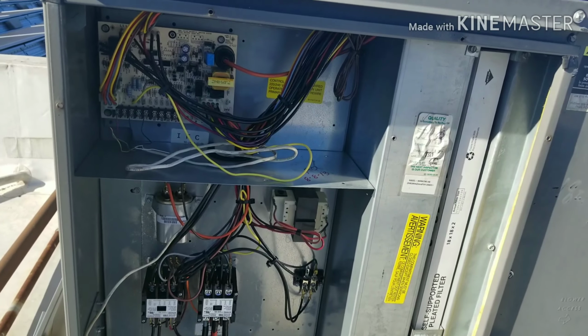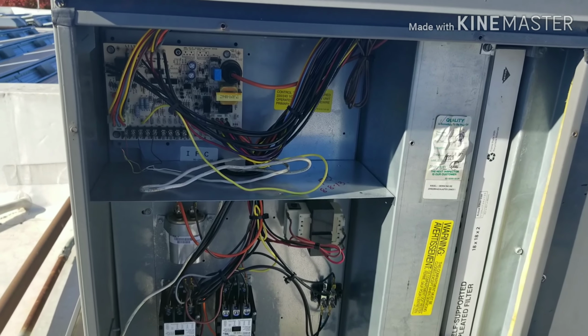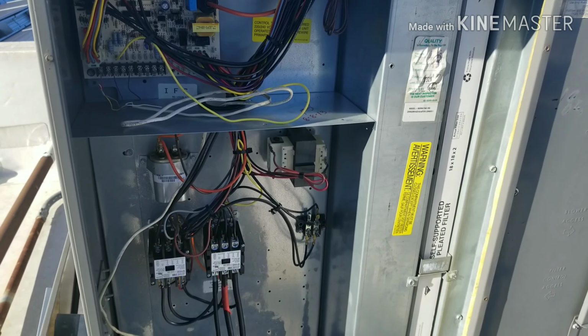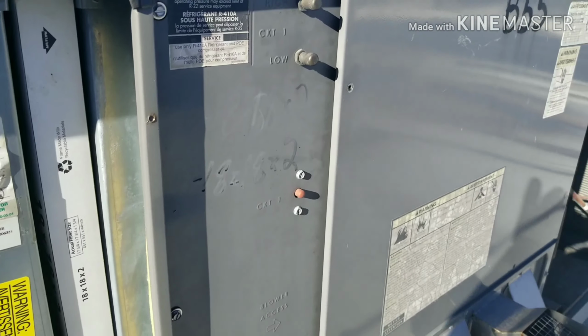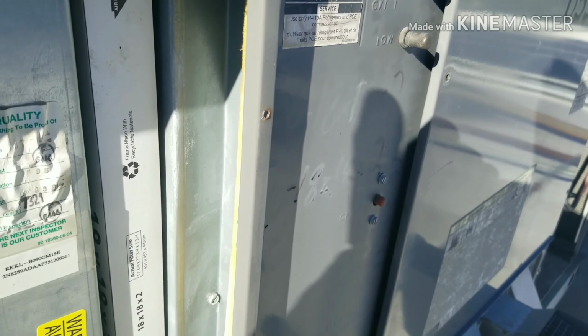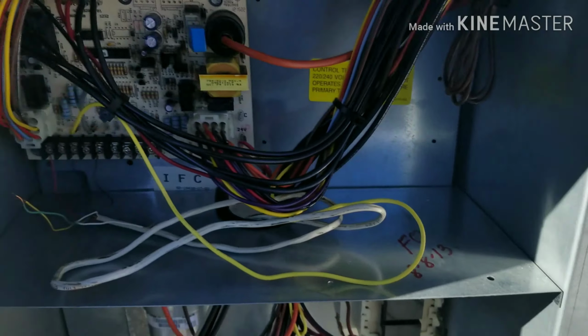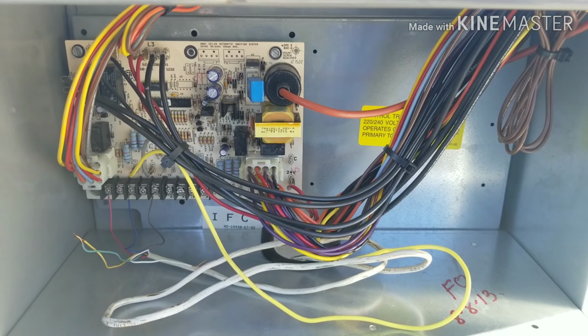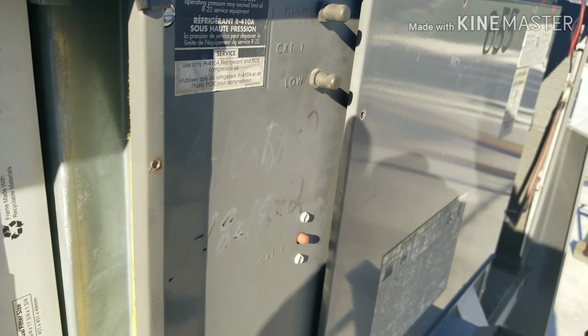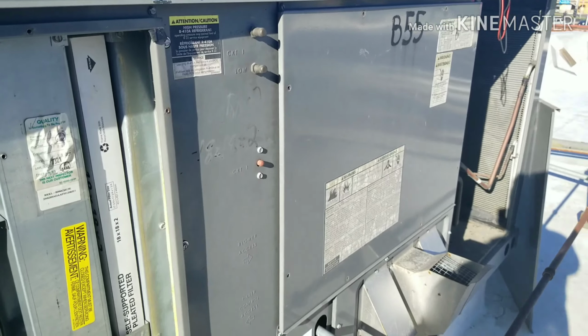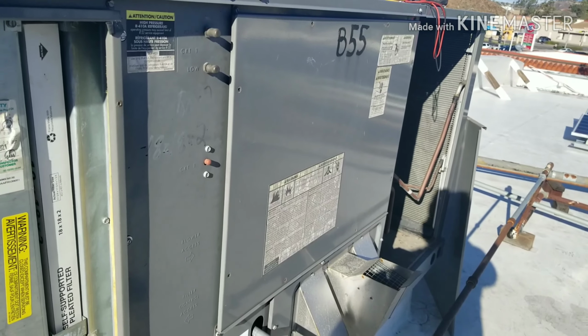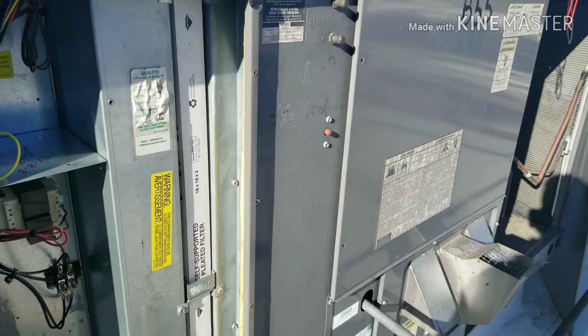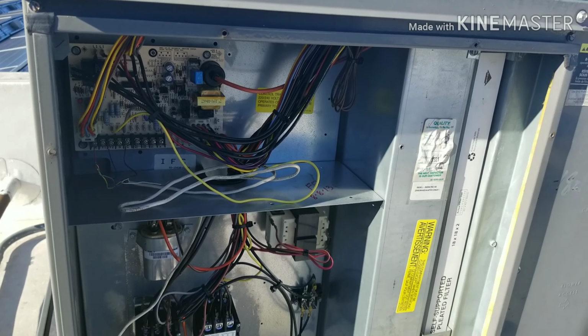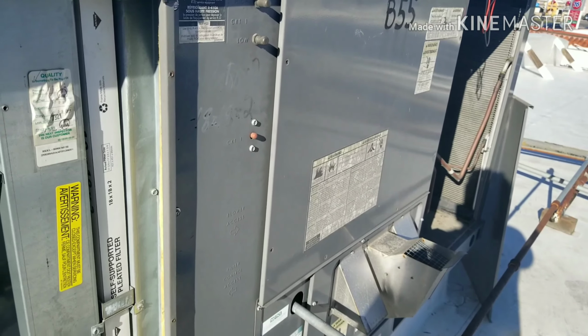So I already took the jumper off the cooling mode to test the cooling, and you can hear the fan running, and that'll run for a predetermined time, whatever the board wants it to, and it does the same thing for heating. Once you remove the jumpers or the heating mode is off, the fan will continue to run.